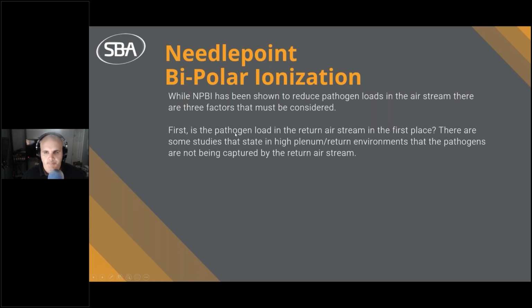So that being said, the return airstream and the supply airstream, when they're too close to each other, like you can't see it, but my supply duct is right up there and my return duct is way back there. So I actually get some decent mixing here in this room. That being said, in certain spaces, you don't get that mixing. Or if it's a high plenum or a high return, then the pathogens may not be captured by the return airstream. And if they aren't captured by the return airstream, then this technology is really just filtering the outdoor air and whatever it's getting out of the ceiling.